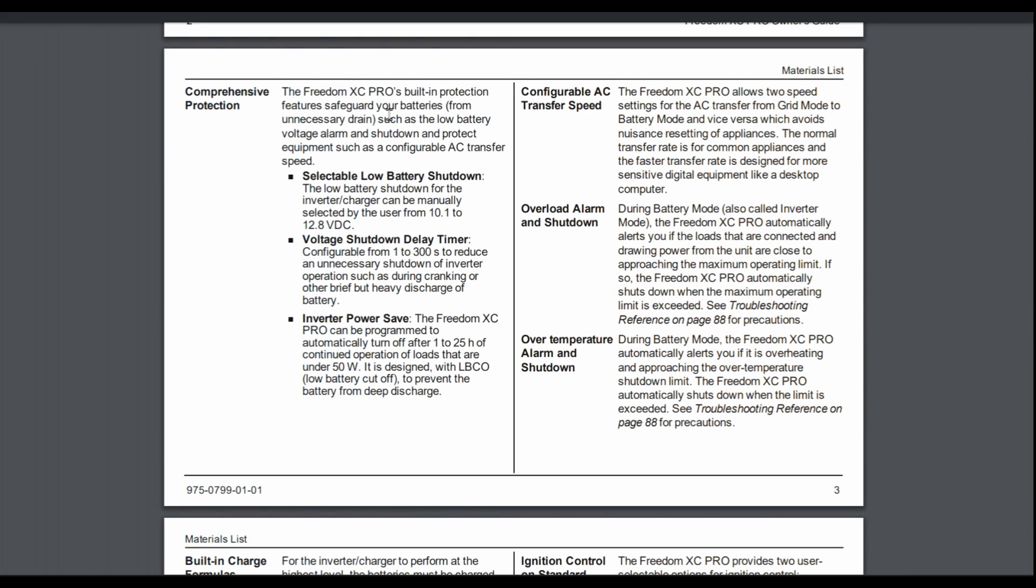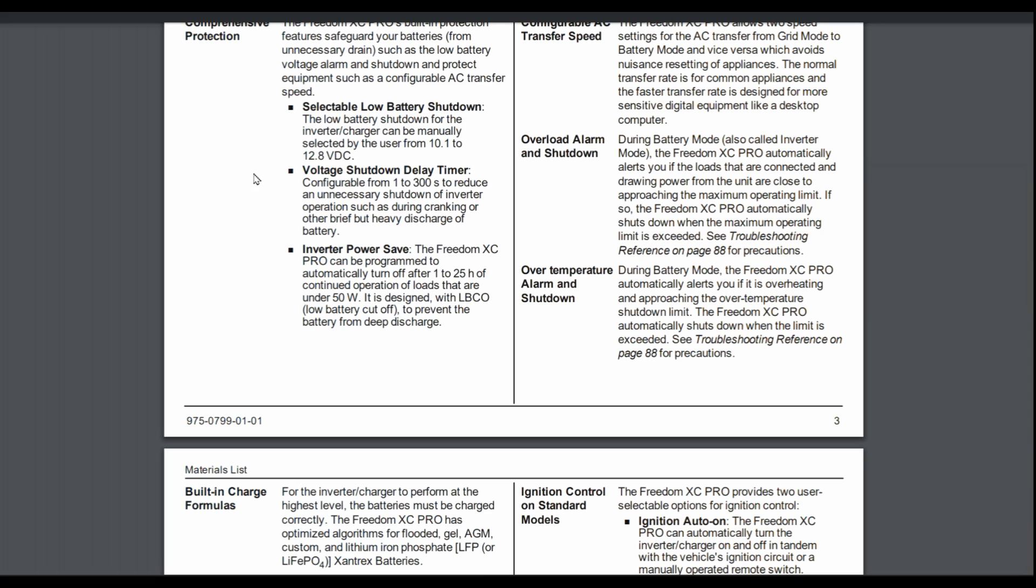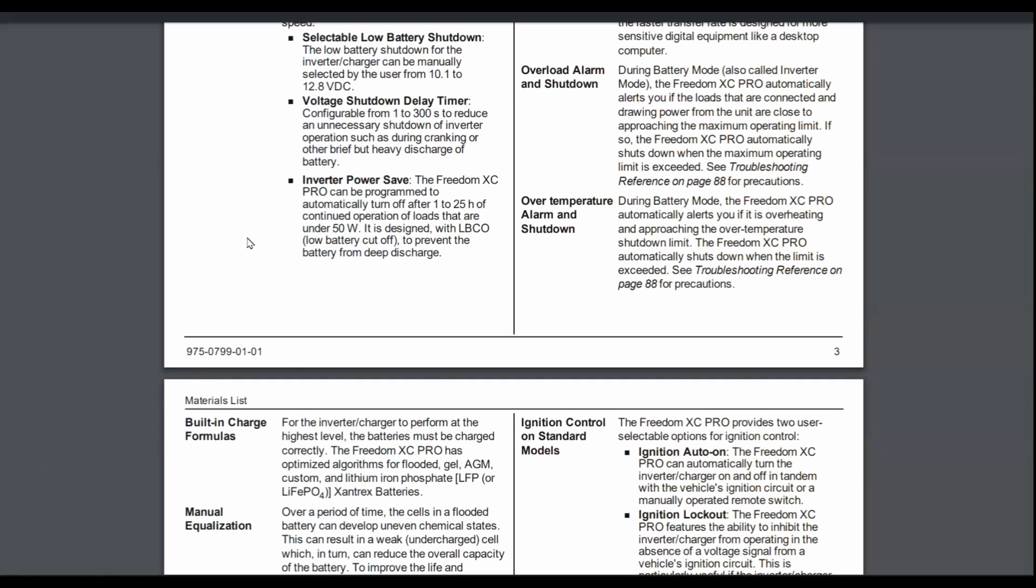Over here we've got built-in protection for your batteries, low battery voltage alarm and shutdown. So if your batteries get too low, it'll automatically stop drawing power from them before they go too low. It has a voltage shutdown delay timer. So a lot of times if you're running a microwave or something like that that's taking an instantaneous draw, sometimes the batteries will sag in voltage just temporarily, so you don't want the inverter to shut down right away under those conditions. So you can configure that from 1 to 300 seconds.